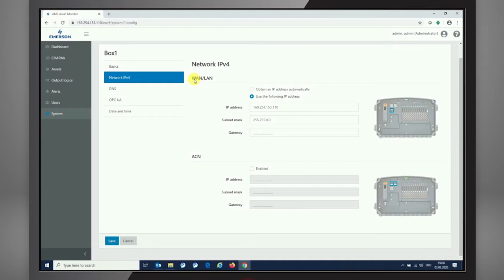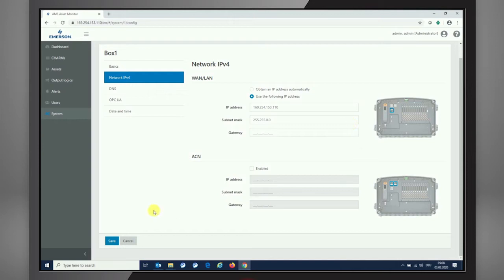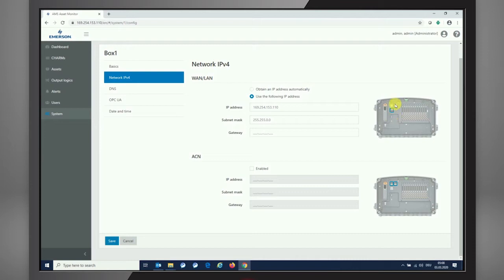Either for the LAN port, which is the lower one port of the three different TCP/IP connections and RJ45 connections that the box is providing, or the ACN setup, which is the upper two ports that are switched together inside for daisy-chaining boxes together from network connectivity perspective. So you see that these two parts of the asset monitor box, the lower network connection part and the upper two parts or connectors, can be handled in different ways.